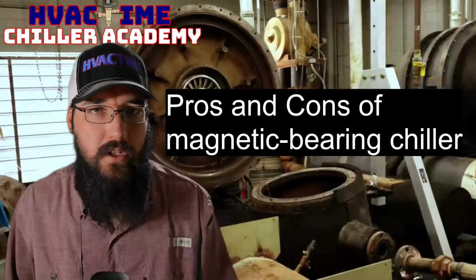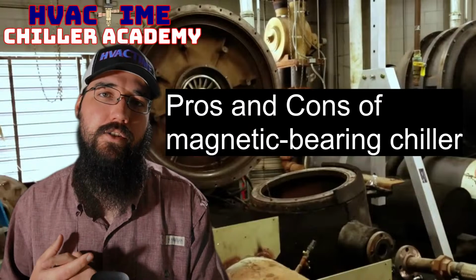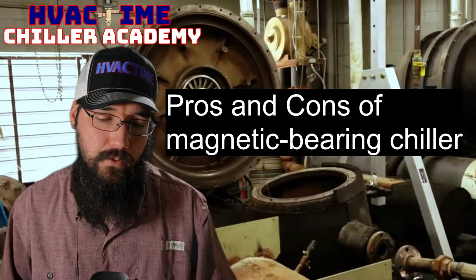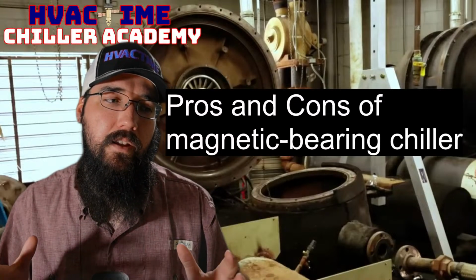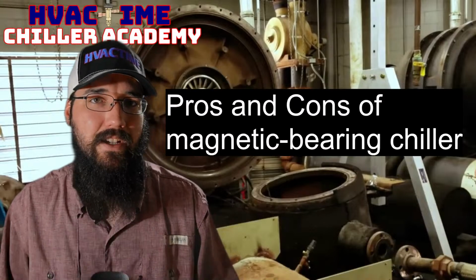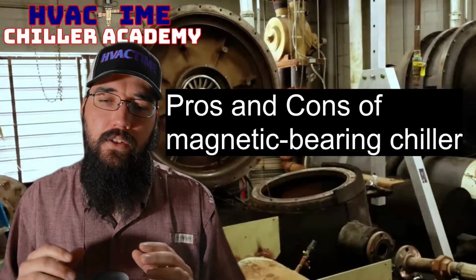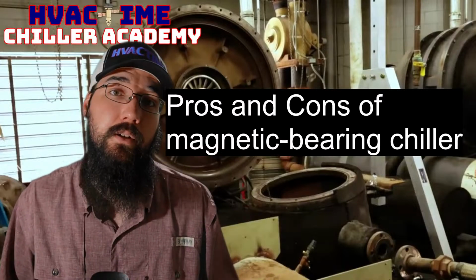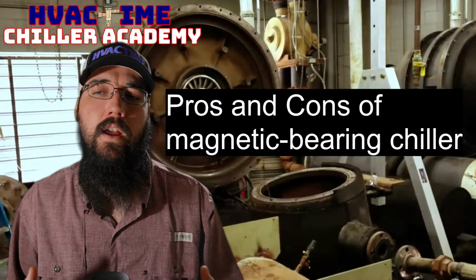Now, there's a lot that plays into that. We're still dealing with a fairly new technology, and there's a lot going on around the development of mag bearing systems. These systems are extremely sensitive to electrical instability in a building, in a space, from the grid. If you have a lot of instability, which a lot of buildings do, especially in major metros, you don't have the cleanest power in the world.